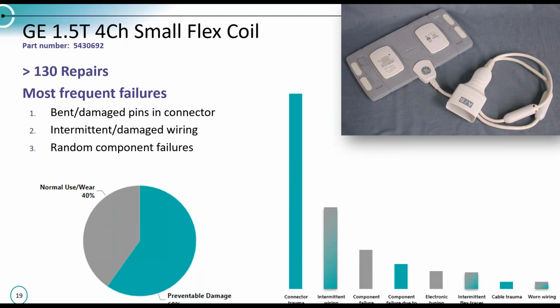So here's another smaller flex coil by GE, and it's a small 4-channel coil. Again, high volume, 130 repairs on this model. By far, the connector encounters the most type of damage here. And I have to speculate, just because it's large and cumbersome, it takes a tumble to the floor a lot of times. And so whether the connector housing is physically damaged or the pins become bent inside the connector themselves just from rushing around, this is where the highest failures occur.